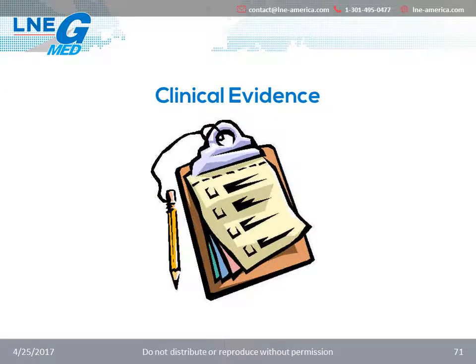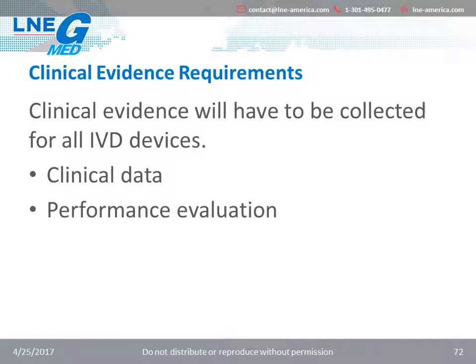Clinical evidence. Clinical evidence requirements will have to be collected for IVD devices. Clinical evidence is defined as clinical data and performance evaluation results pertaining to the device of sufficient amount and quality to allow a qualified assessment of whether the device achieves the intended clinical benefit and safety when used as intended by the manufacturer. The new regulation makes the need for clinical data and performance evaluation more explicit and prescriptive.